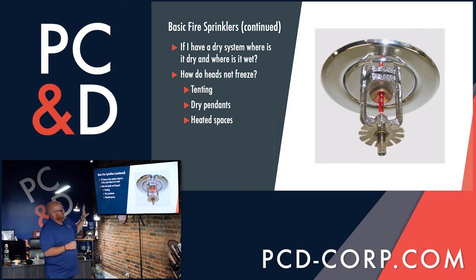So we went pretty deep on the sprinkler side because, in my opinion, this is one of your more critical and important systems in your entire building. At the end of the day, this is the last resort to save us from a catastrophic loss of life. So make sure you know how your sprinkler systems work. Make sure you know whether or not they're wet or dry. Make sure you know where your low point drains are.